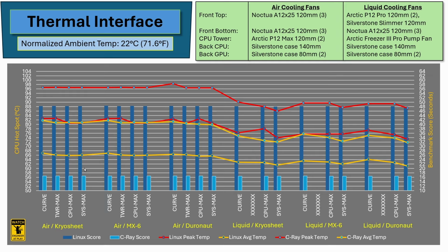Taking a quick look at this data, if I focus just on air cooling, there isn't a lot of variance from changing the thermal interface. Maybe if we squint really hard, we can see some measurements that are lower on the Duronaut thermal paste, but it's not a large amount—if anything, probably just a degree Celsius. On the peak side of things, it looks pretty flat to me. I'm not seeing much change across them all.